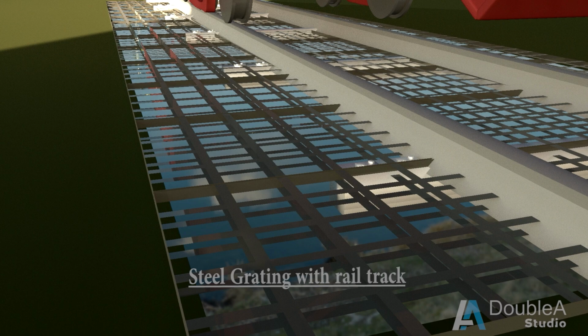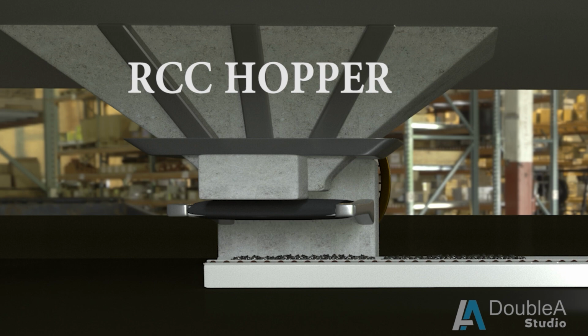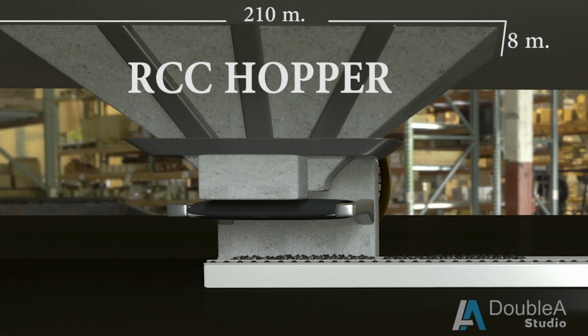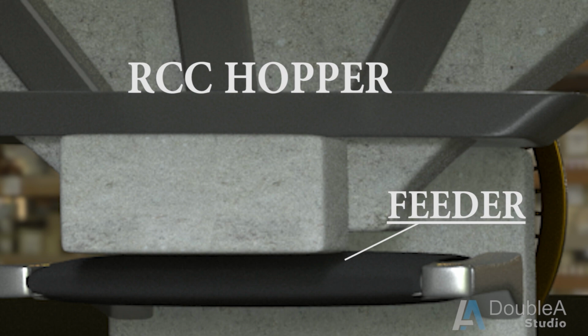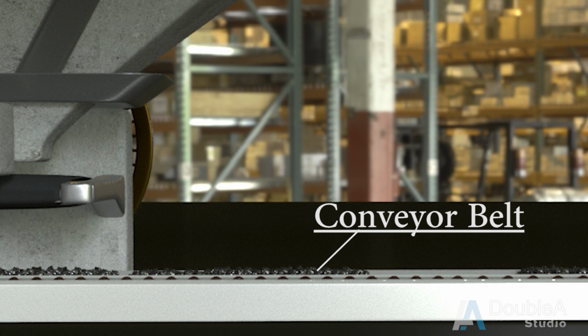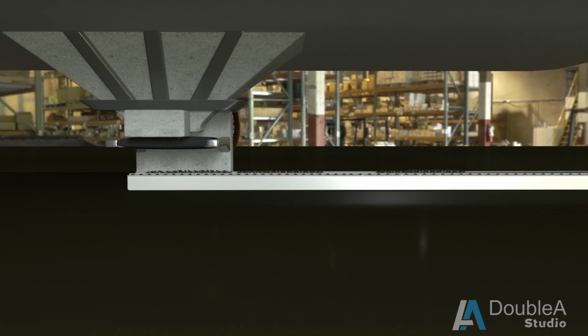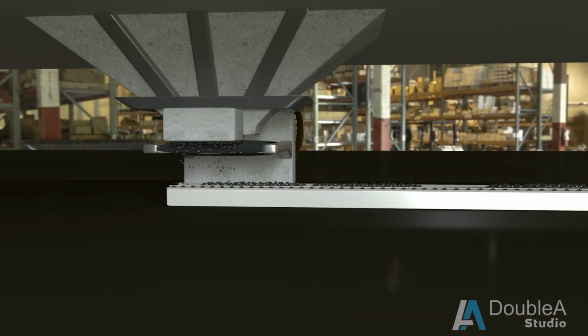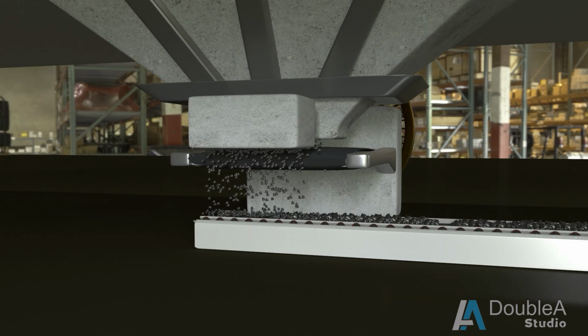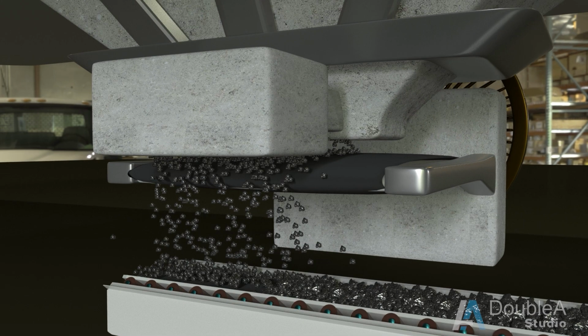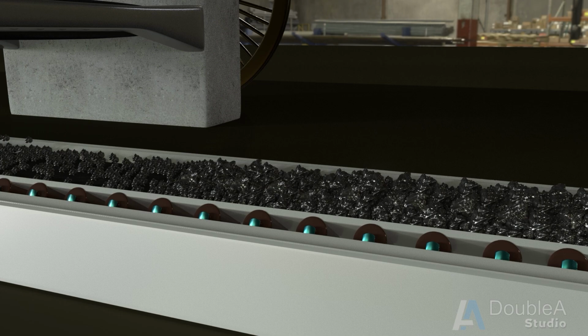Now we come to the track hopper. It is made from a large number of mechanical items like steel grating covering the RCC hopper along with the railway track, RCC hopper of 210 meter length and 8 meter width, feeder at the discharge side of the hopper, and conveyor belt located at the discharge of feeder. Hopper is a V-shaped RCC container to hold and discharge coal through its bottom chute. Below it, feeder is located which feeds coal to the conveyor belt.